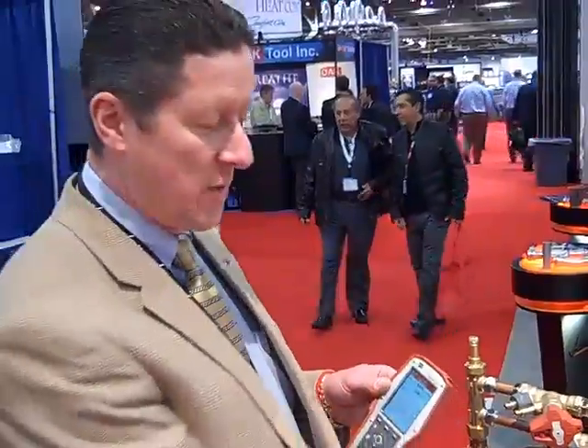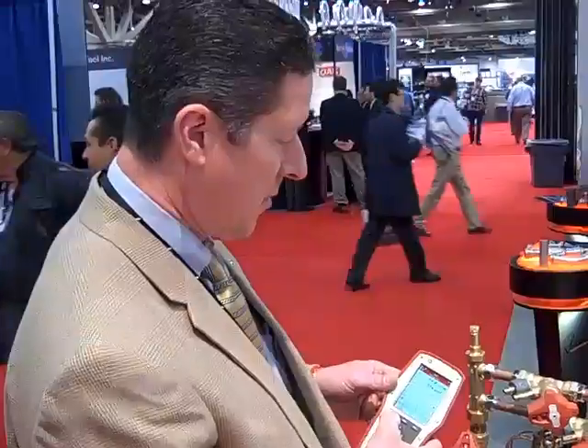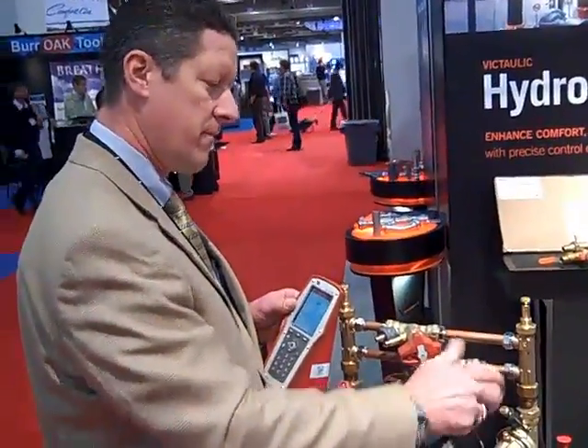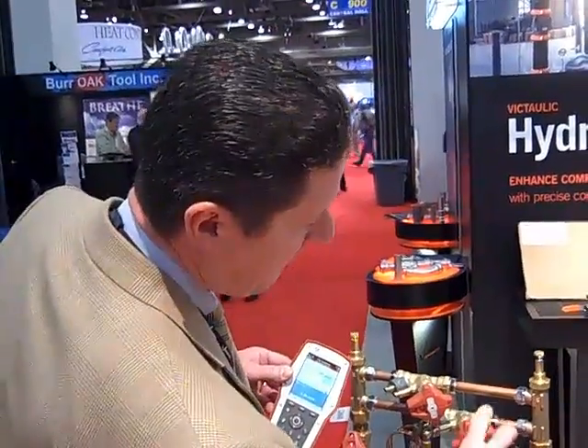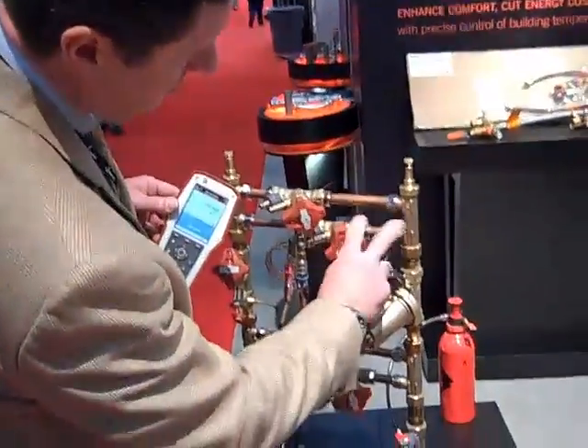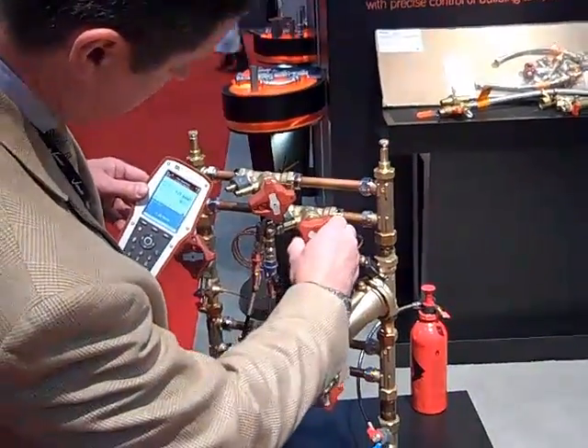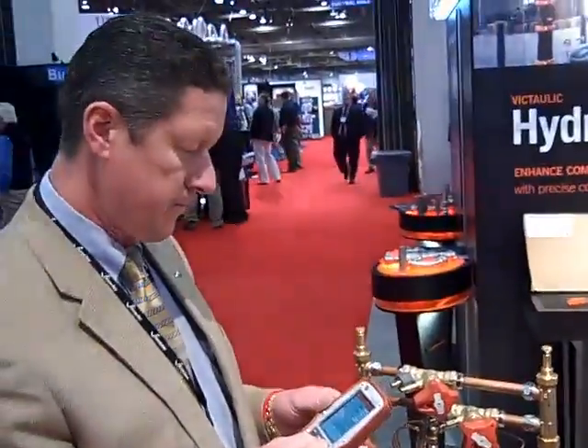Now, we're at 81% of design flow, so if we want to reset this, we can adjust the handle and the hand wheel position here till we get 1, or we can do the computer method, where we hit options, computer method, and we shut the valve quickly. It takes a differential pressure reading on that valve with it shut. We hit done, continue, and adjust it to 2.28 turns. So we open that valve right back up to 2.28, continue. We're at 0.991 GPM. That's how fast we can reset it.